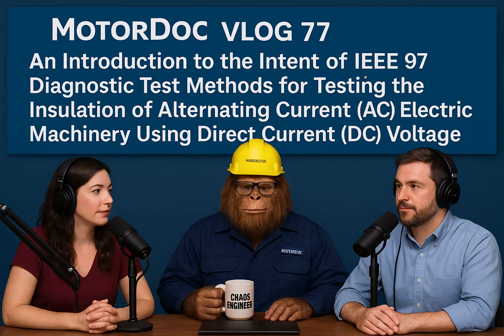that other factors can significantly mess with these DC test results. You have to consider them when you interpret things. Oh, absolutely. If you ignore these factors, you could completely misdiagnose the situation. The primary ones are, first, the type of insulation materials used in that specific machine. Different recipes of epoxy or polyester or whatever respond differently.